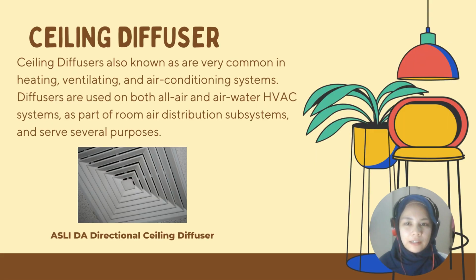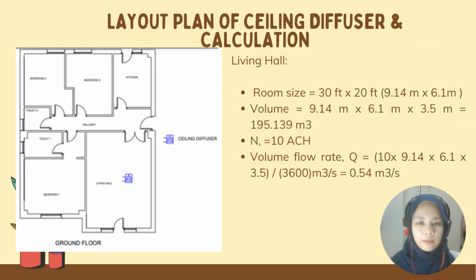Ceiling diffuser, also very common in heating, ventilating, and air conditioning systems. Diffusers are used on both all-air and air-water HVAC systems as part of the room air distribution subsystem and serve several purposes. For ceiling diffuser, we are using ASLI DA directional ceiling diffuser. This is our layout plan of ceiling diffuser and calculation.